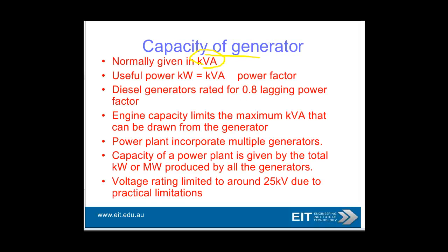Capacity of generator is normally kVA, 1,000 volt amps, that's a small k, and you find that useful power, kilowatts, is 0.8 times the kVA. So you've got your good old triangle power, and the useful power is the kilowatts, which is this little bottom part here. This part here is your kVA, and this, which we're not going to discuss here, is kVAR, which is reactive power.